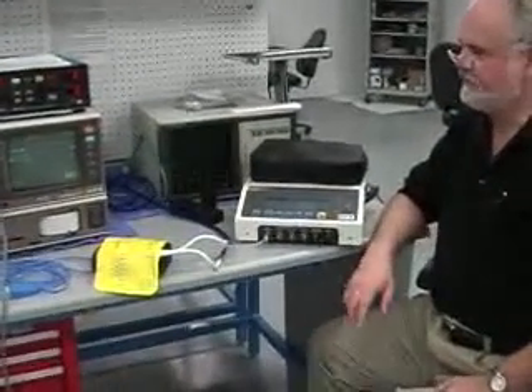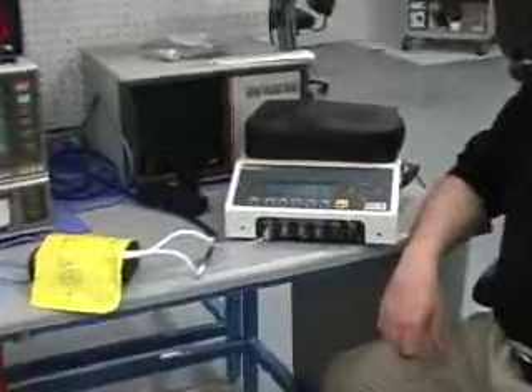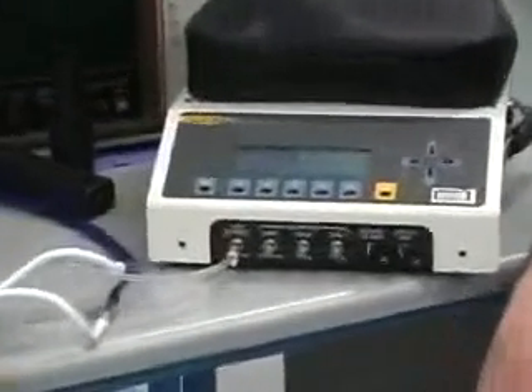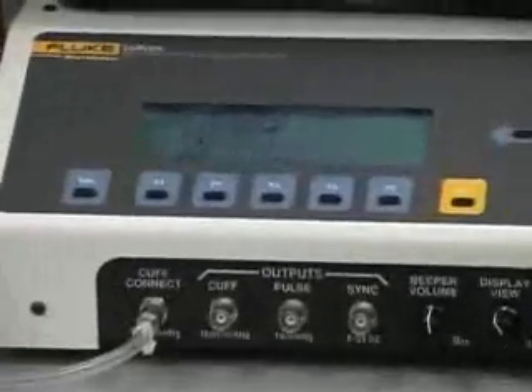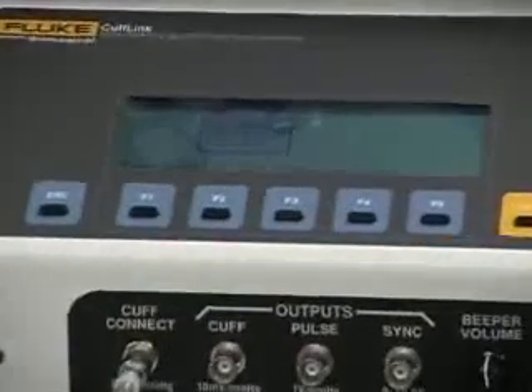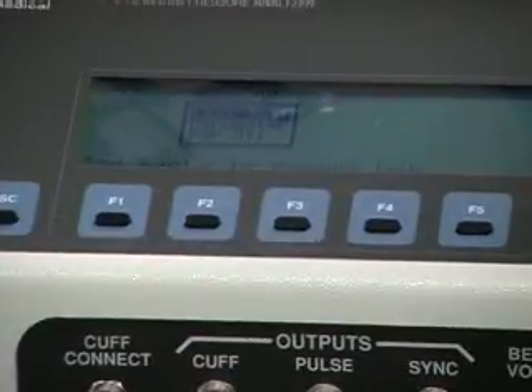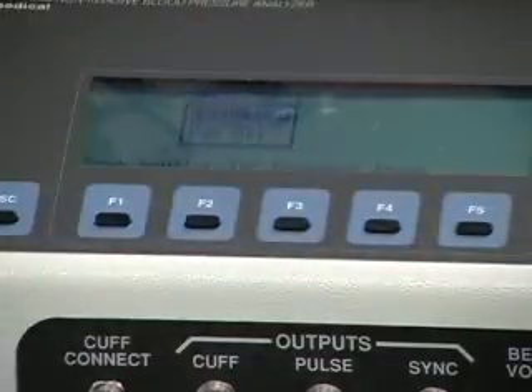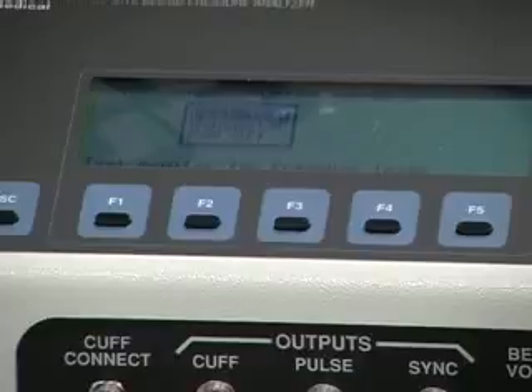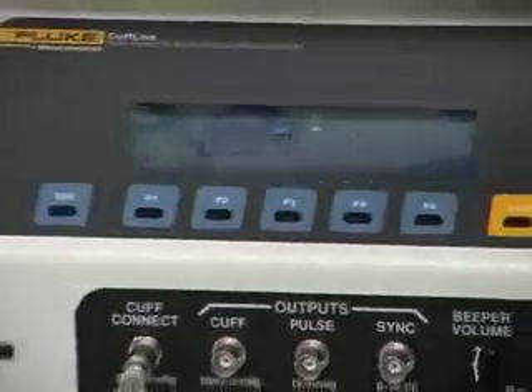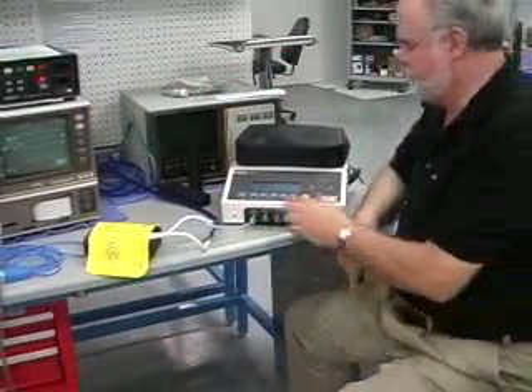And pop-off basically is that the compressor in the unit is running, and possibly if there's a problem with it, you want to make sure that there's a relief valve in the unit so that it opens this cuff line to atmosphere, because you don't want to sit there and cut the circulation completely off on the patient's arm. So to run that test, we'll just reset this again. Okay, we're ready to go.